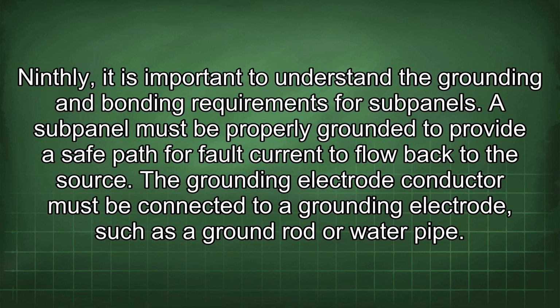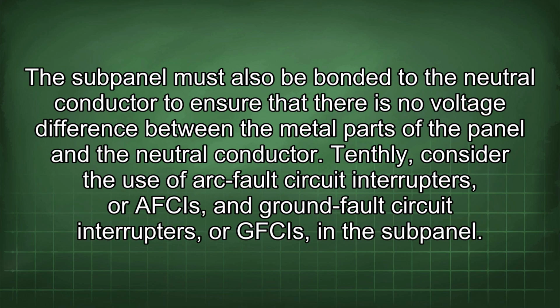Ninthly, it is important to understand the grounding and bonding requirements for subpanels. A subpanel must be properly grounded to provide a safe path for fault current to flow back to the source. The grounding electrode conductor must be connected to a grounding electrode, such as a ground rod or water pipe. The subpanel must also be bonded to the neutral conductor to ensure that there is no voltage difference between the metal parts of the panel and the neutral conductor.